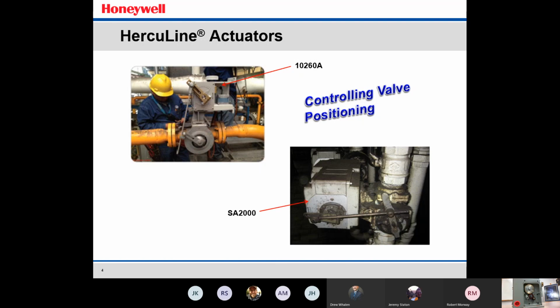On the bottom right-hand side, that's a picture of a Herculine 2000 actuator. You can see it's a little bit smaller butterfly valve there, possibly a port valve, but again, connected with the linkage arm there and a rod connecting it to the butterfly valve. Probably in that top picture there is an example of a startup where the technician's probably using that auto/manual switch or hand wheel right at the actuator in order to set up that linkage.